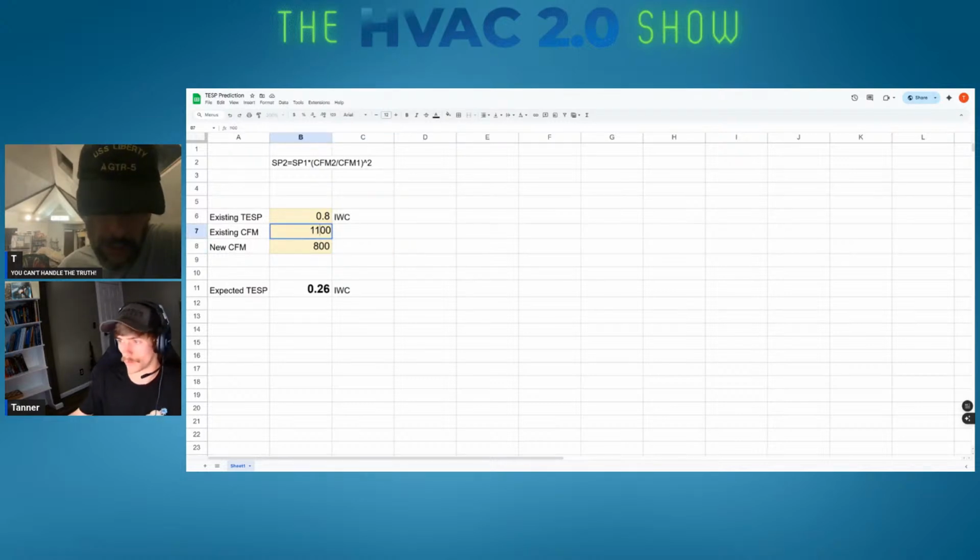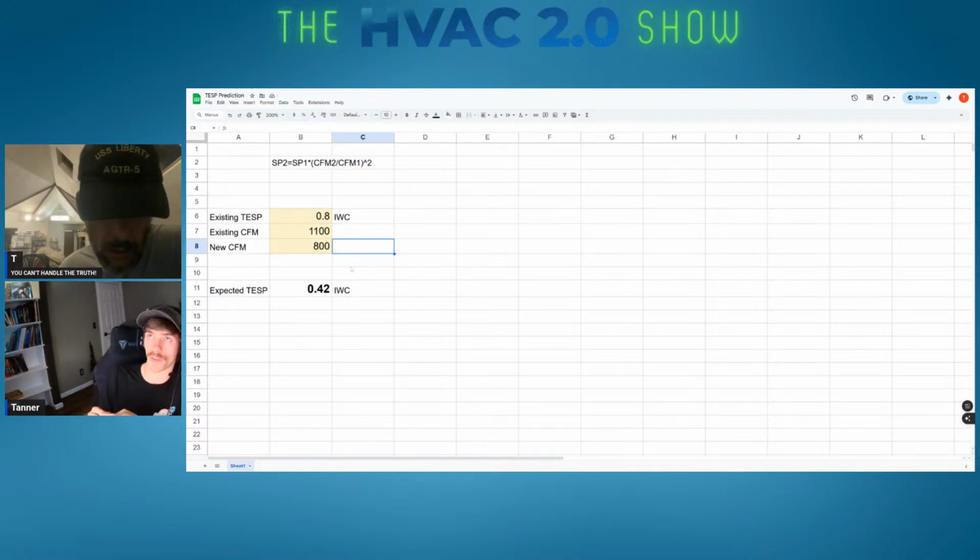Measure Quick would tell you that because it would tell you delivered capacity. Measure Quick can, yes, with the psychrometers, estimate that airflow. There's been other people who say it seems to be very accurate. I've not tested it enough to be able to say for sure. But that's the kind of thing, if you have a true flow grid, you're clearly going to use it because that way you can have a much higher level of confidence.